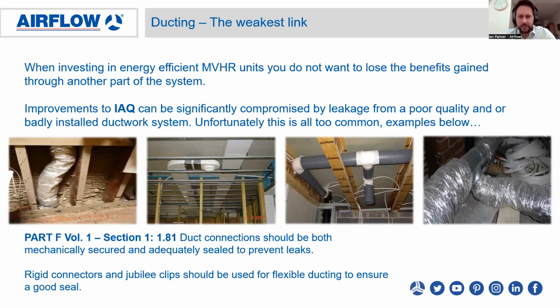And there's a number of issues if you don't get the ducting system right. Part F, Volume 1, refers to the duct connections, and says they should be both mechanically secured and adequately sealed to prevent leaks. Rigid connectors and Jubilee clips should be used for flexible ducting to ensure a good seal, because if that ducting starts leaking, it increases the pressure of the ventilation system and reduces the performance.